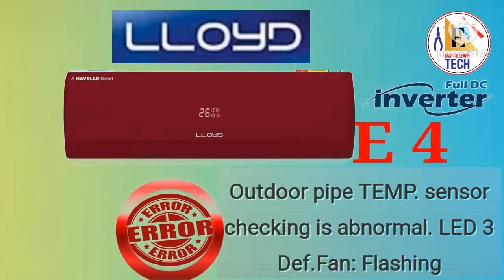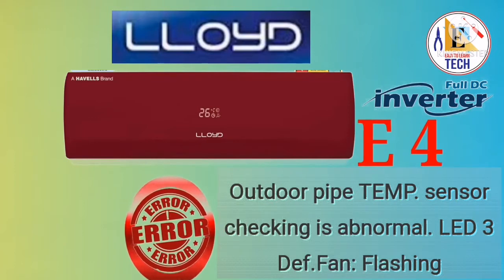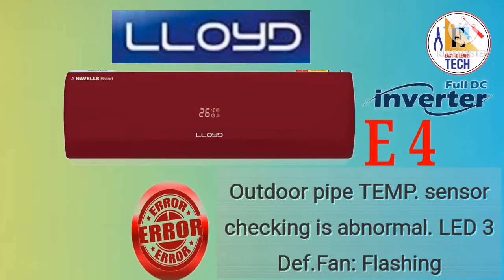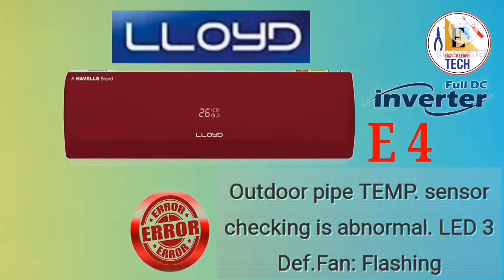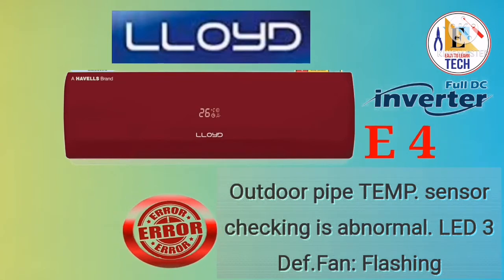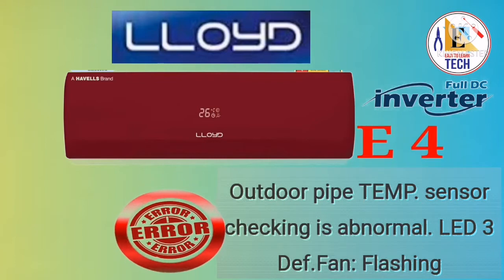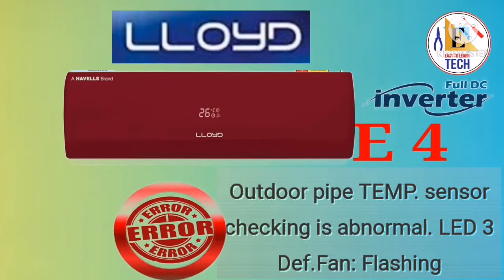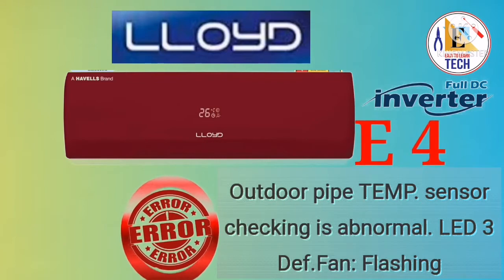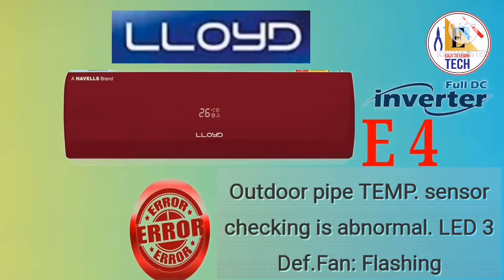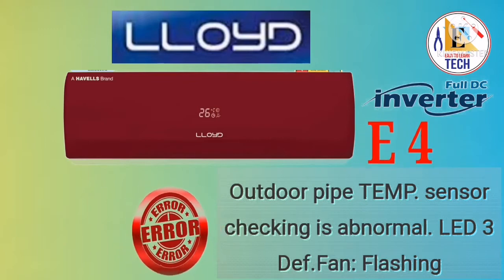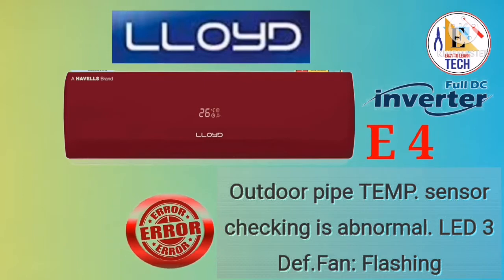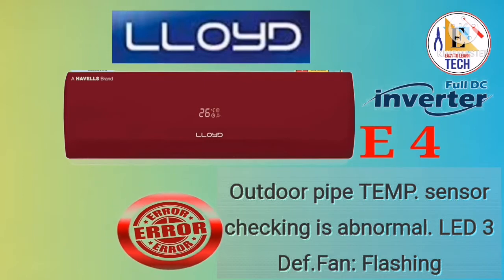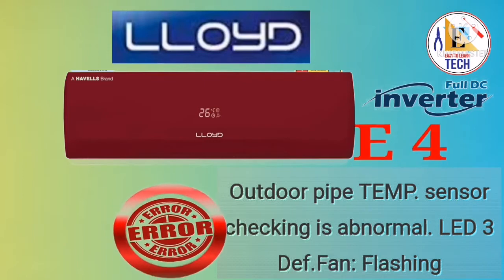When you see E4 or LED3 fan flashing, it means outdoor pipe temperature sensor faulty. The outdoor pipe temperature sensor is installed on the condenser coil of our outdoor unit. You can see it near the compressor. When you see this error, you have to go directly to the outdoor pipe temperature sensor. Then you have to check the connection, the wire between the sensor and the zip, and whether the zip is properly connected to the PCB or not. Then you have to check if the resistance is good or not.